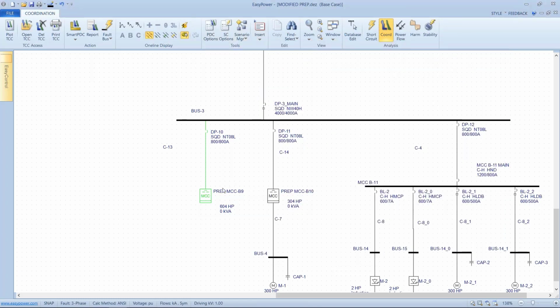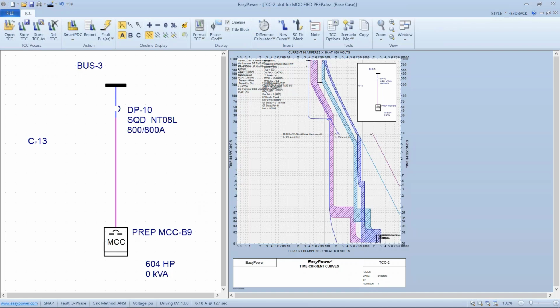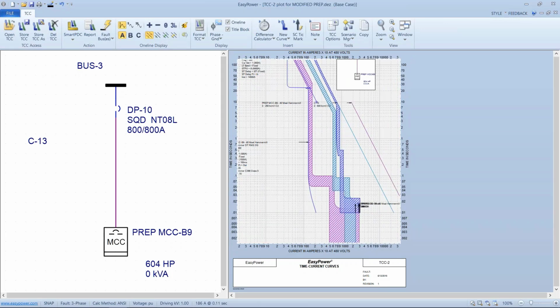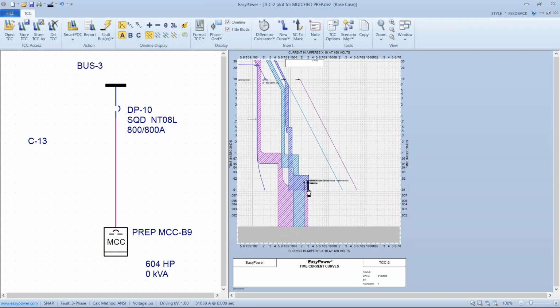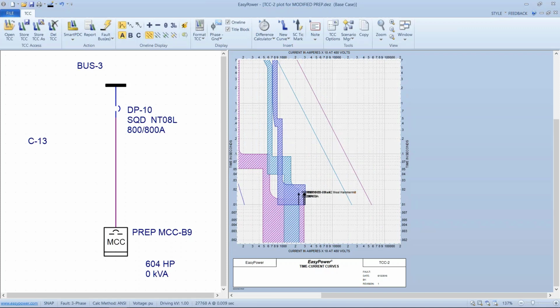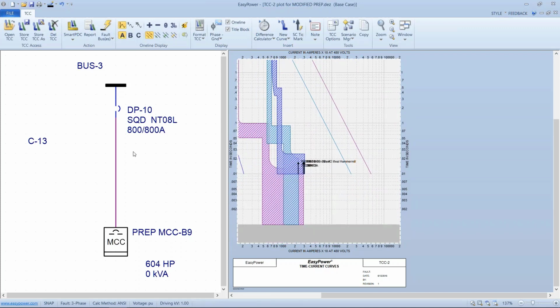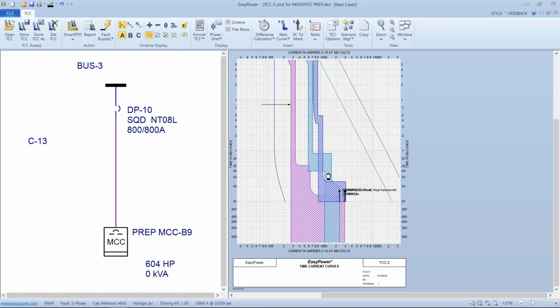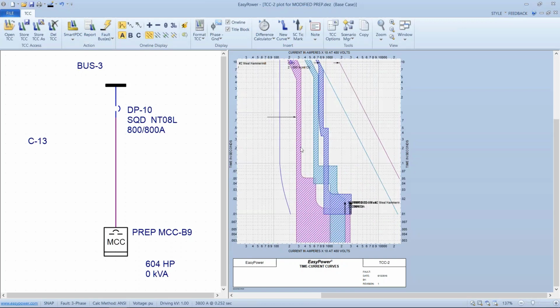So the point to be made is that I can coordinate the main with the breaker above it, and that's what we're looking at when we plot the TCC, but I can't do much about coordination for this motor. I can look at it, but I can't see that it's not necessarily coordinated. But from the looks of things, we're pretty close. Now the good news is Smart PDC can accommodate it, and if we invoke Smart PDC, it does make some adjustments. In fact, it pulled out my breaker from the motor starting curve because there was some overlap.